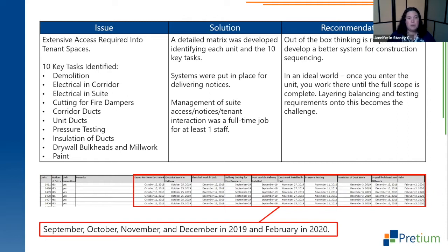In an ideal world, you'd enter a unit and complete the full scope of work before leaving. But when you layer in balancing and testing requirements, that becomes really challenging, because those tests have to happen once a larger section of the mechanical system is complete. For example, we can't insulate until we've pressure tested the ductwork. So we couldn't find a way to enter a unit for just a couple of weeks and be finished with them.